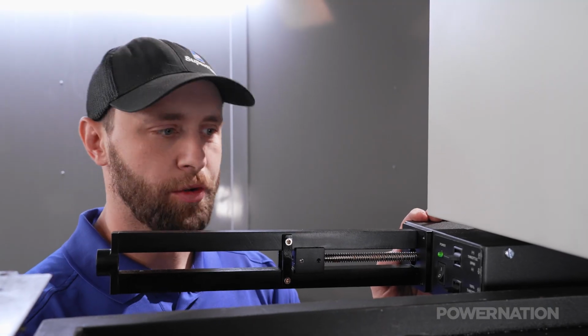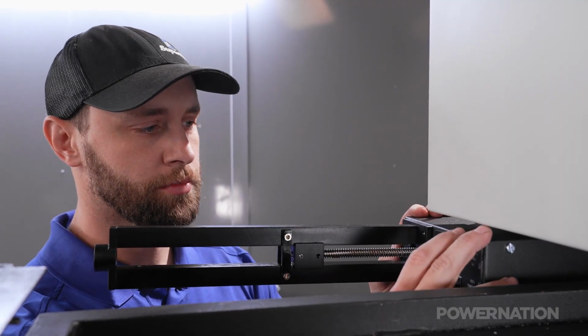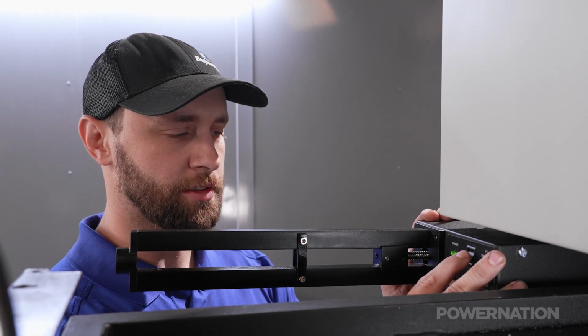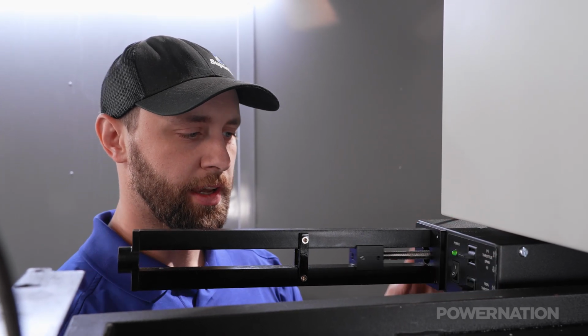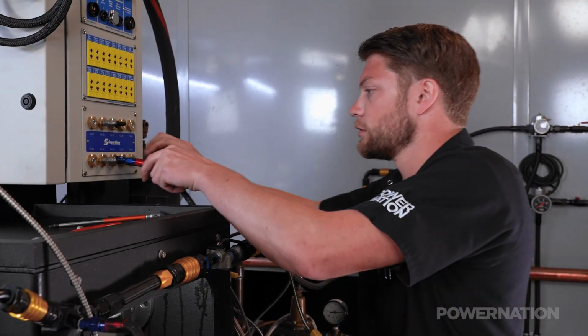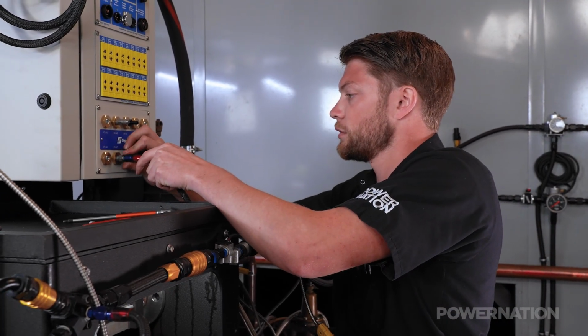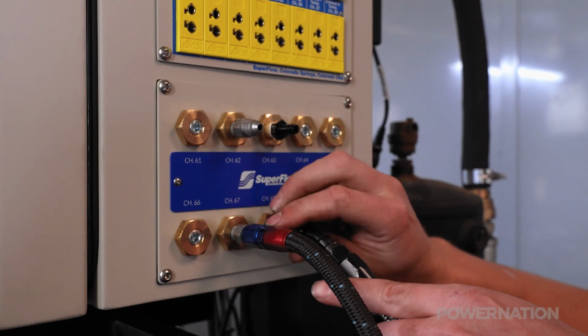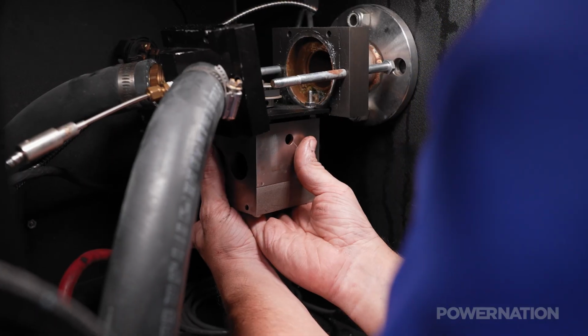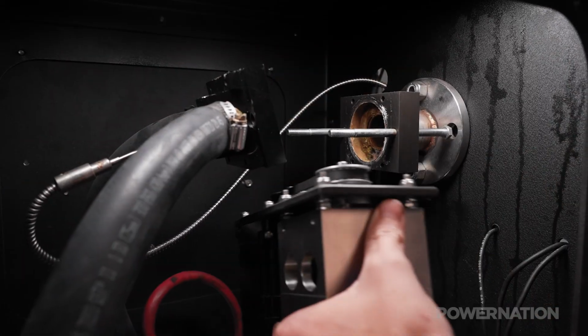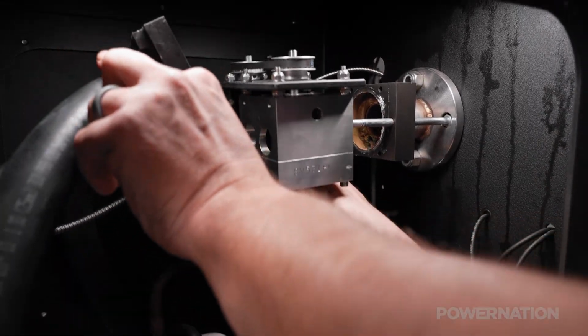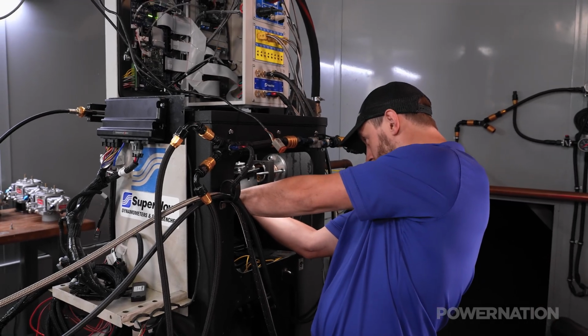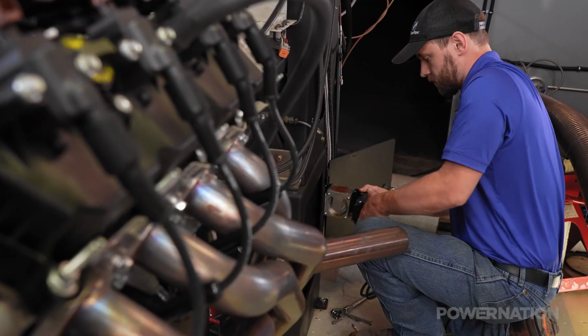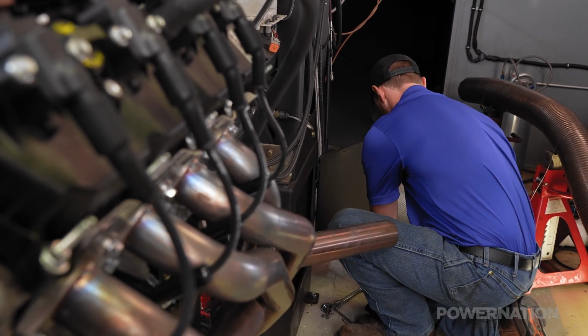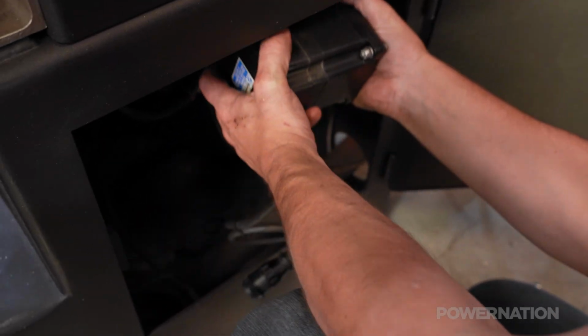So I'm setting up the auto throttle in manual mode right now. Going to 100%, adjusting the span, making sure that's moving, and going back to our 0 position. The input and output connections are made and our pressure sensor lines can be installed into the new transducer ports. Along with all new sensors, we are also getting new servos that pair with a software to help improve the control of the dyno. The upper is located just above the dyno's absorber and controls the water entering the brake, and the other, the outlet, is just below the absorber.